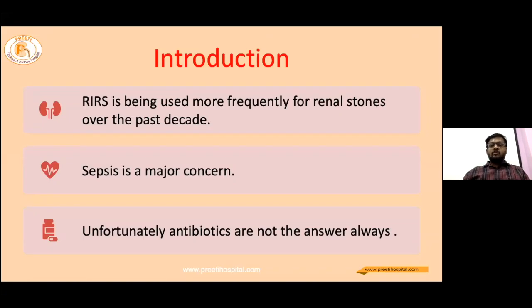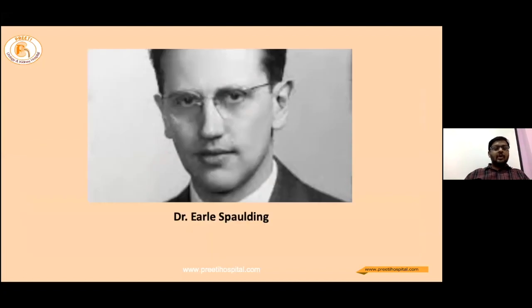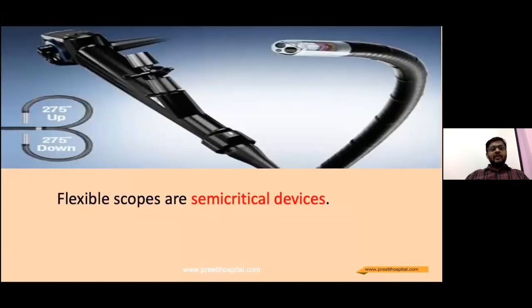RIRS is being used more frequently for renal stones over the past decade. Sepsis is a major concern. Unfortunately, antibiotics are not the answer always. According to Spaulding's classification, all our flexible scopes have been classified as semi-critical devices which require either sterilization or high-level disinfection.